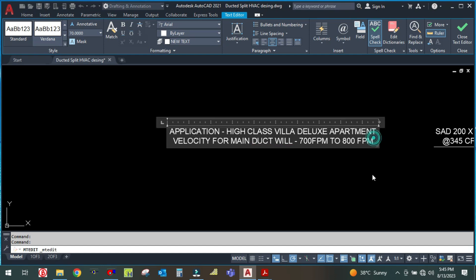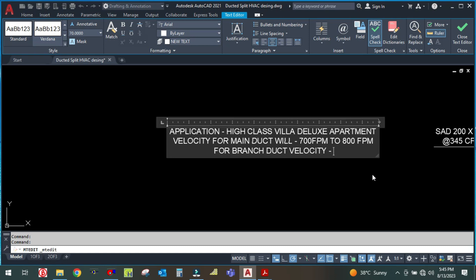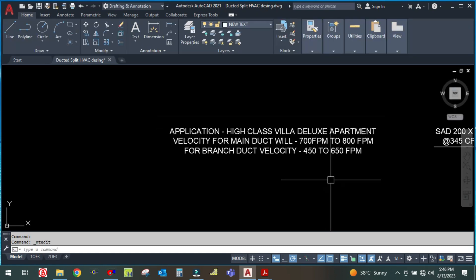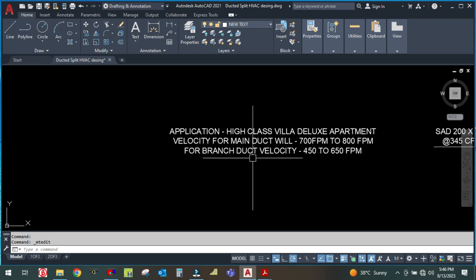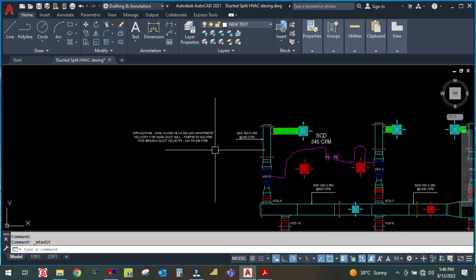For the branch duct, the velocity will be 450 to 650 feet per minute. These are the conditions we have to follow.